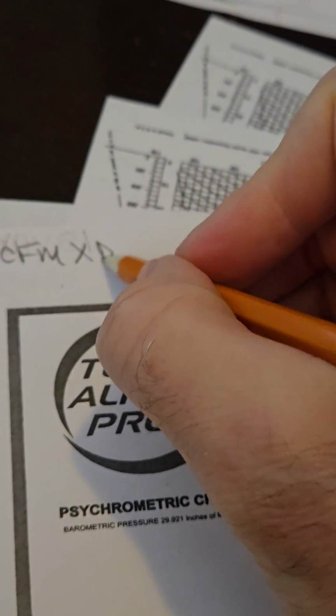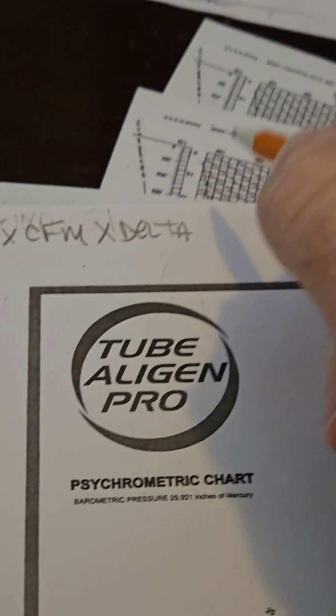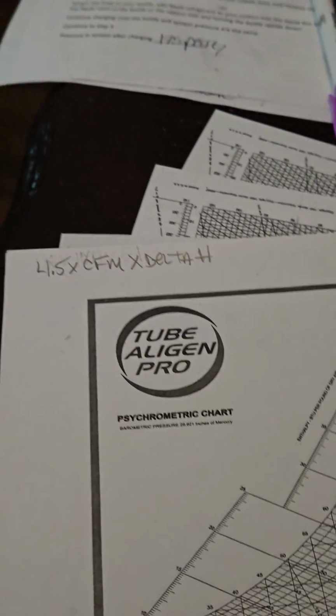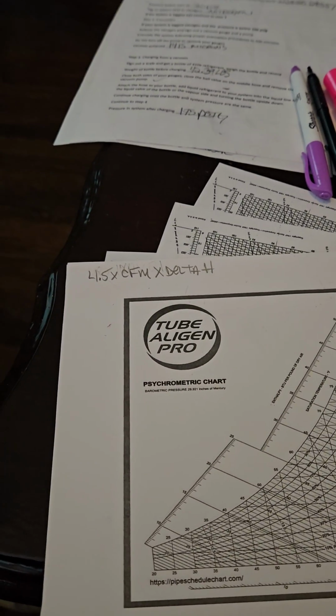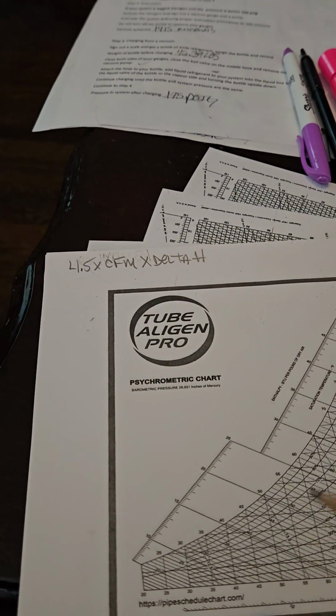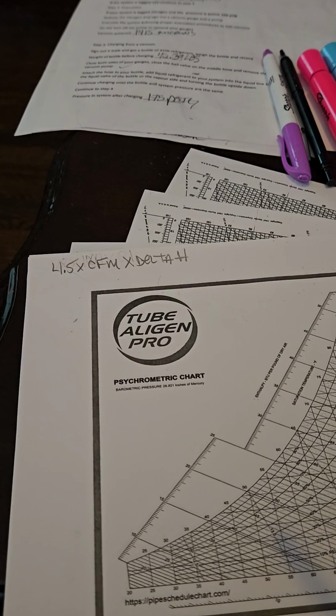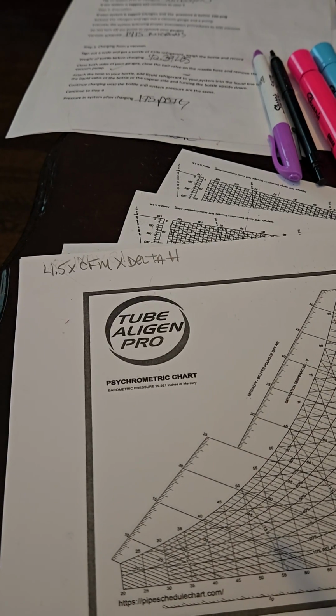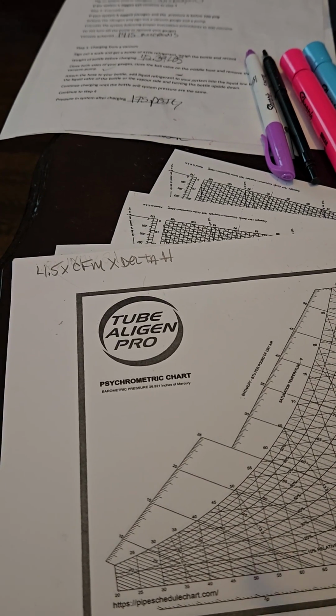So total heat is 4.5 times CFM times delta H. Okay, so we need to figure out what delta H is. Delta H will be the difference in the BTU output in that moment.